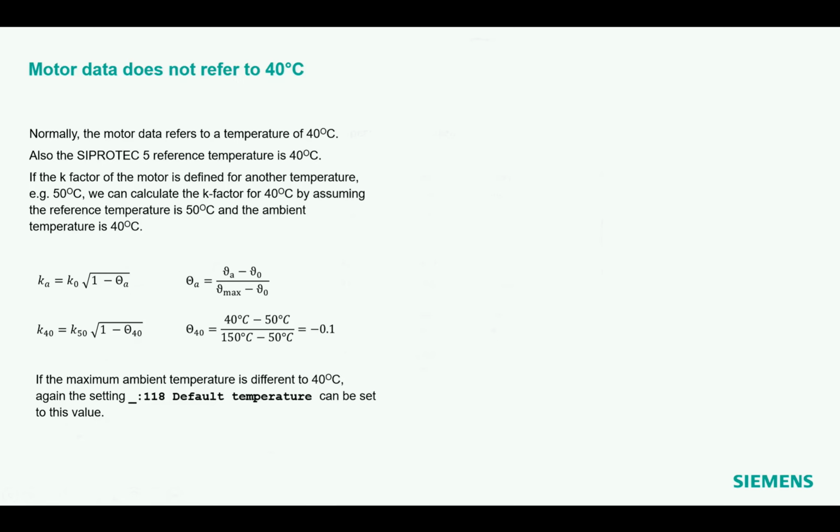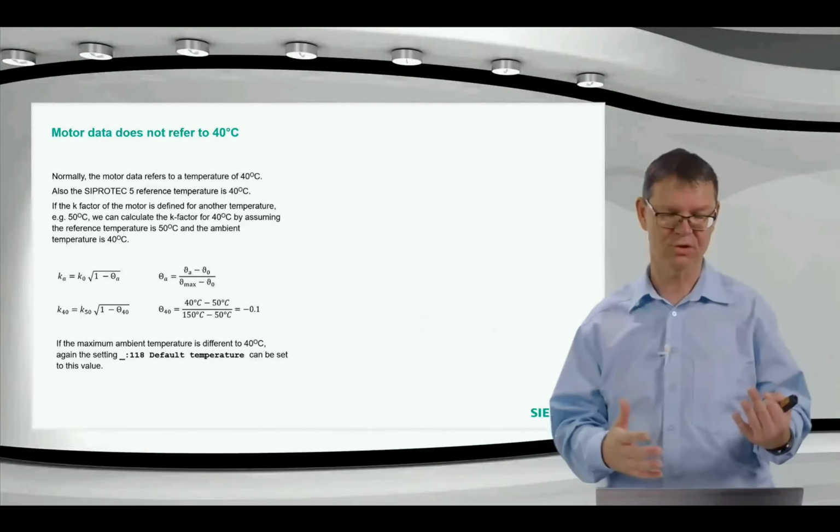I found out again 2 other relays. I don't want to explain them here. They are equivalent. You get different temperatures, relative temperatures, different end temperatures. Even the interesting thing is the tripping time is identical from each preload situation. So I would say basically we have, I found at least, 3 different principles of setting this situation. I choose this one to present because I think this is the most logical one.